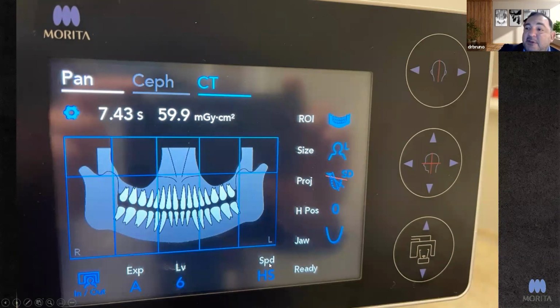Basically, on the high definition panoramic image, you're going to acquire double the amount of base images than the high speed one. So you're going to have a much higher resolution panoramic. But the trade-off is that the reconstruction time of that panoramic image is going to be higher. It's going to take longer. That's why you don't want to use the high definition for scout imaging, although you could, because in reality it's going to take much longer for the image to actually pop up and allow you to aim at the area of interest. So just be mindful of the acquisition time here. High speed, 7 seconds; high definition, 14 to 15 seconds.